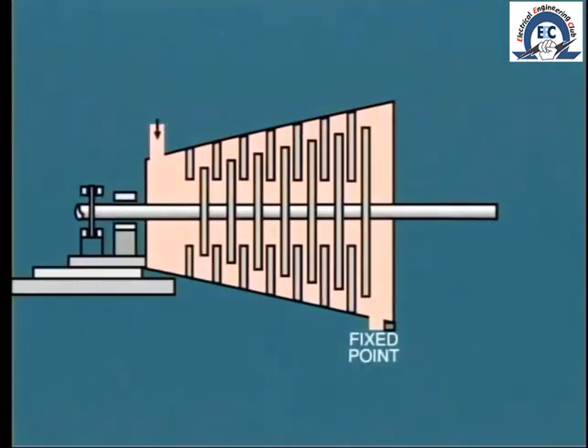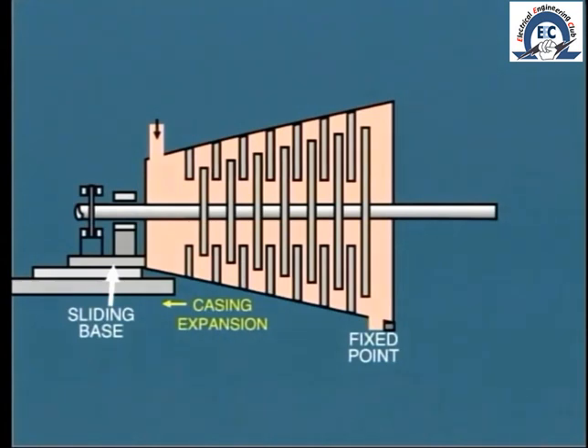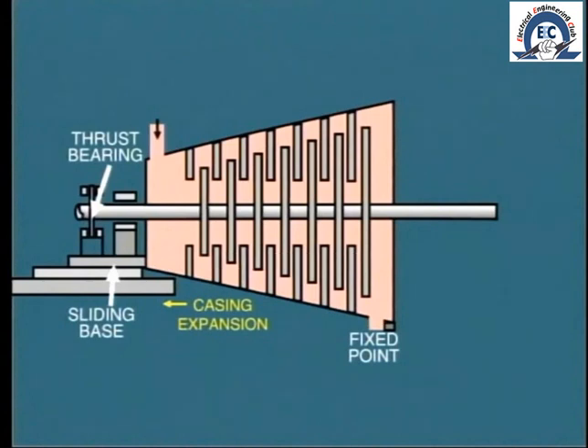We have already seen how the turbine construction allows for the shell to expand axially, usually on sliding feet at the governor pedestal. Now, while this is happening, the rotor is expanding but in the opposite direction. Remember, the high pressure end of the rotor is secured by the thrust bearing.